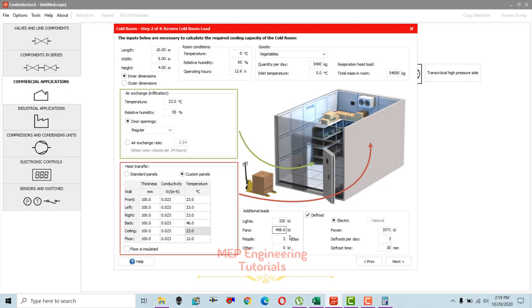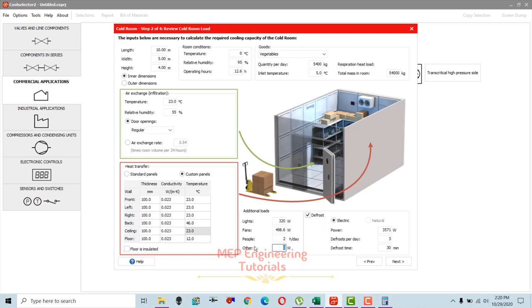Based on input parameters, fan power is automatically calculated at approximately 500 watts. For people load, you need to specify how much time people will spend inside — storing material and removing goods for usage. Since door opening is set to regular, we keep this at two hours per day. If door opening were rare, we could set it to one hour per day. Any additional equipment loads can also be added here.